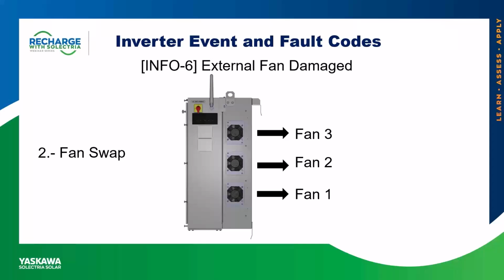So basically, if fan number 2 is running with the unit off, we grab fan number 2, we put it in the position of fan number 3, and vice versa. Fan number 3, put it in the position of 2, and fire up the inverter. If the code changes, and now it's showing fan 2 feedback error, and the middle fan stopped working, you know the issue followed the fan, and it's a bad fan that needs to be replaced. Now what happens if we do the fan swap, but the issue remains in the same position? Well, this may be a voltage issue or a wiring harness problem.